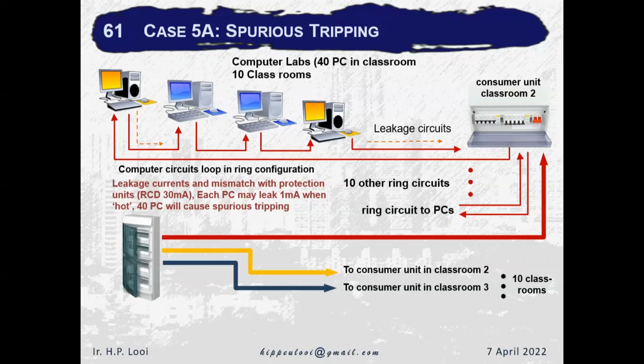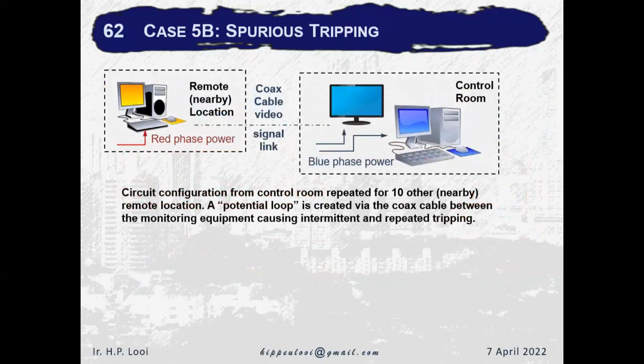So what happened is, usually one computer has a leakage current of 1 milliamp when it's hot. So that's why it's intermittent. When it's not hot, it may be less than 1 milliamp. So if you have 40 computers, you have 40 milliamps, and your RCD is 30 milliamps. When you start, maybe no problem. When all the computers are hot and everybody is working, then it starts tripping. And this is another case.